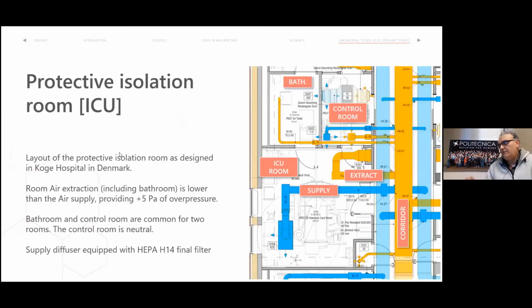This is an example of an intensive care unit for protective isolation. And this is not a lab, this is a control room, and here there are the doctors and the nurses that control how the patient is doing. This is the supply, you see, on the external side of the room, and then we make the supply. This is of course provided with HEPA H14 filters. And here there is the patient, and here there is the extraction, which is made with two grills, one close to the floor and one close to the ceiling. It is more or less like the operating theater, to have a uniform flow of the air. We provide these two differential extractions at two different levels.